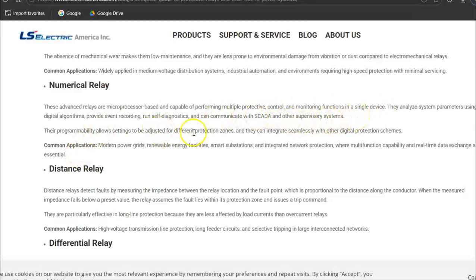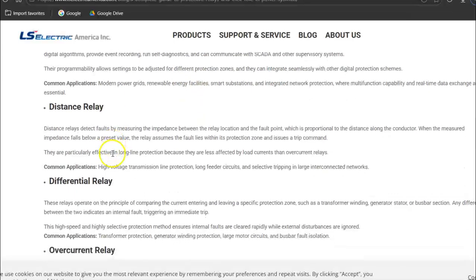And they now even can be set up for different protection zones. Distance relays detect faults by measuring the impedance between the relay location and a fault point. Basically, it measures the impedance across a line, and they know what the impedance is between substation A and substation B. If the impedance changes, they know there's a short or a fault to ground.